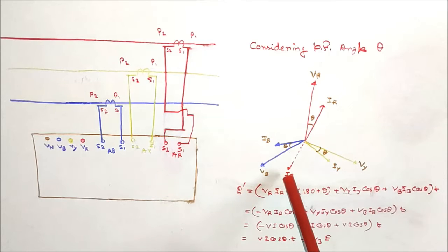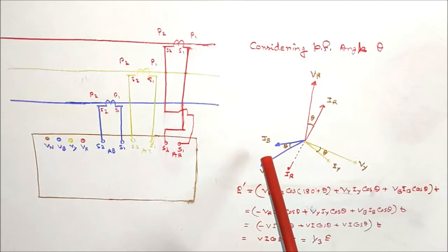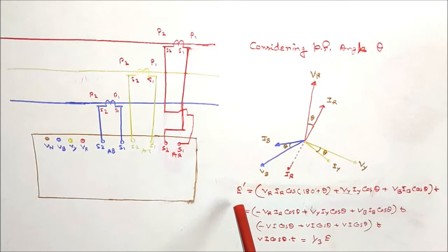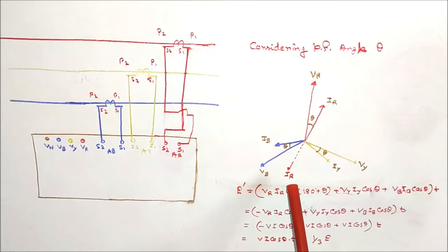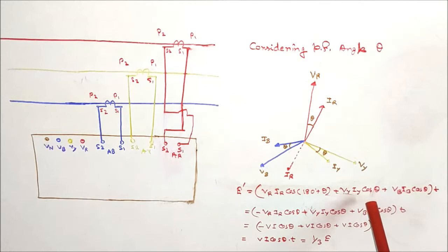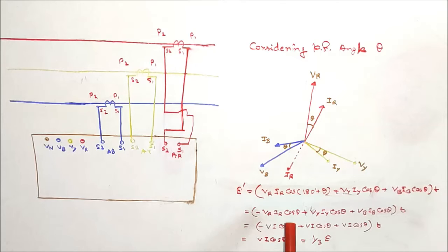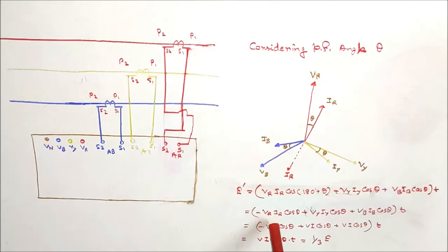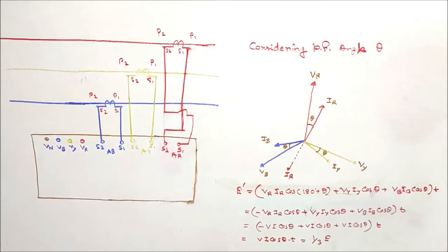Due to this reversal, the red phase current phasor will be 180° apart from its original position, while yellow and blue remain as before. The three-phase energy meter reading becomes: E' = VR·IR·cos(180°+theta) + VY·IY·cos(theta) + VB·IB·cos(theta), multiplied by time T. Since cos(180°+theta) = −cos(theta), this gives: −VR·IR·cos(theta) + VY·IY·cos(theta) + VB·IB·cos(theta), times T.